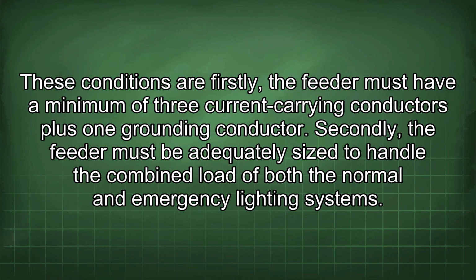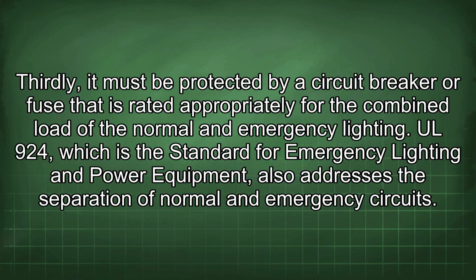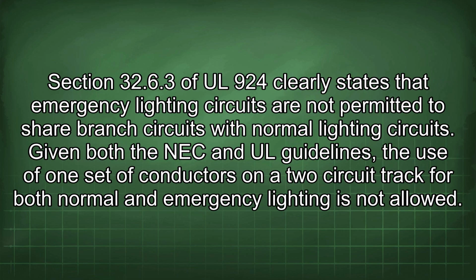grounding conductor. Secondly, the feeder must be adequately sized to handle the combined load of both the normal and emergency lighting systems. Thirdly, it must be protected by a circuit breaker or fuse that is rated appropriately for the combined load of the normal and emergency lighting. UL 924, which is the standard for emergency lighting and power equipment, also addresses the separation of normal and emergency circuits.